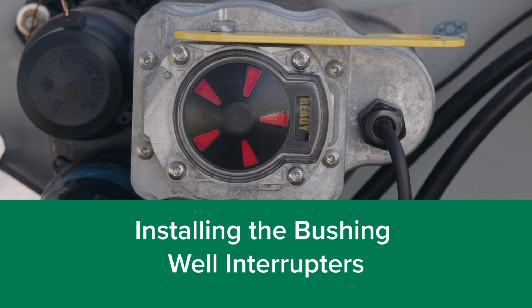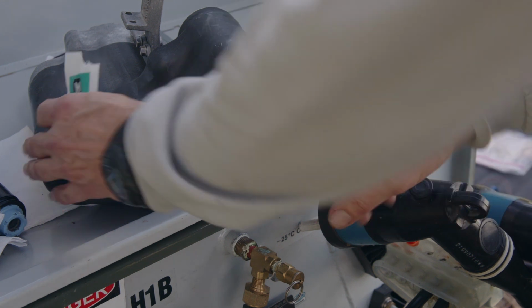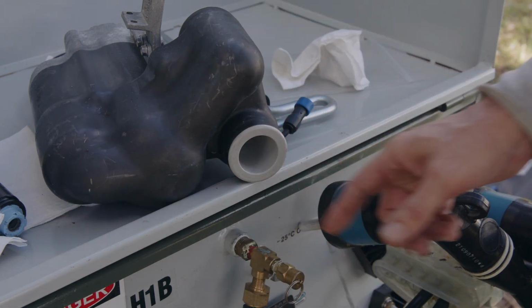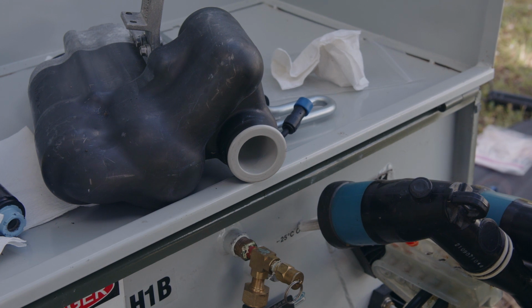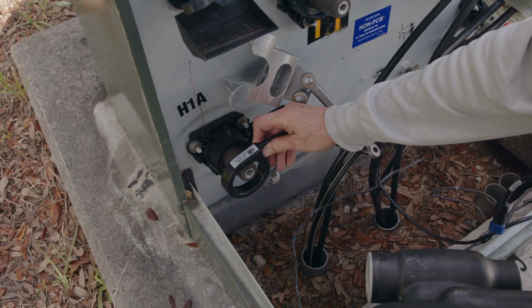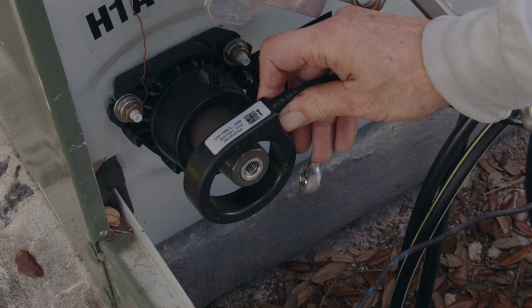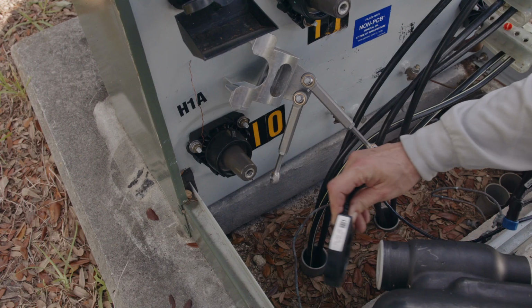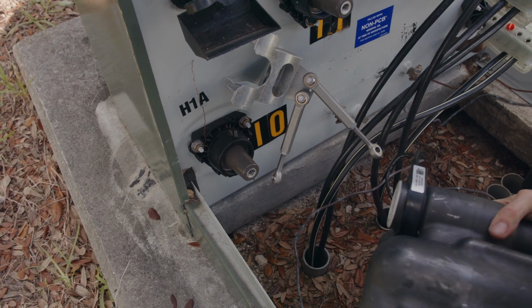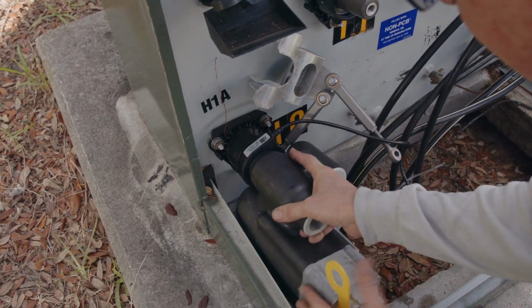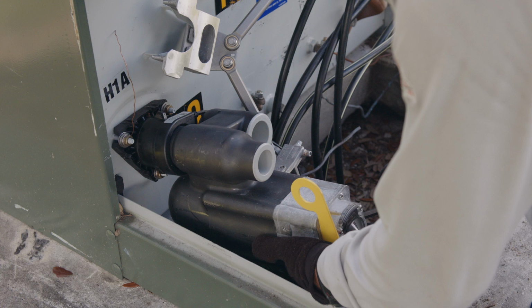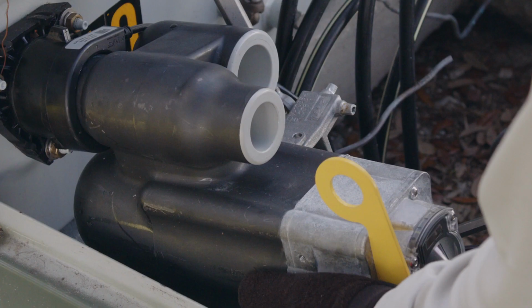Follow these steps to install the bushing well interrupters. Step 1. Remove the shipping caps from the H1A bushing well interrupter. If not already lubricated, grease the exposed taper of the H1A bushing well adapter with silicone lubricant. Step 2. Slide the current sensor onto the H1A bushing well interrupter with the arrow pointing toward the transformer. Step 3. There is a captive bolt inside the bushing well interrupter. Install the bushing well interrupter onto the bushing well adapter with the yellow lever in the vertical orientation.